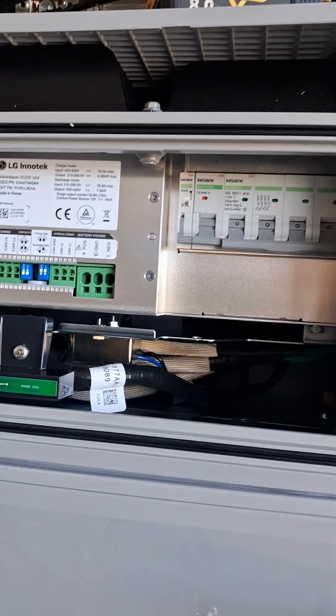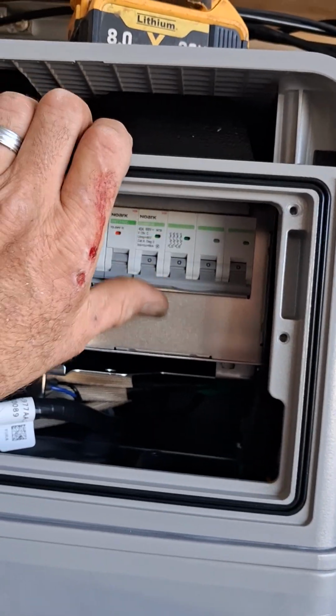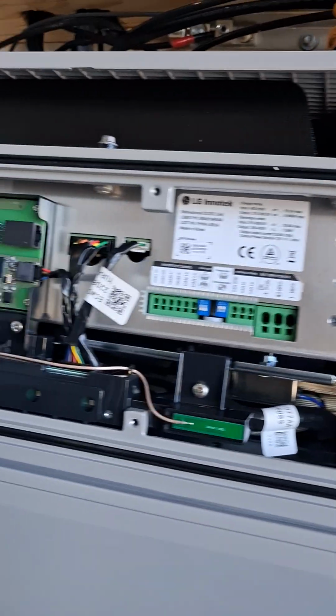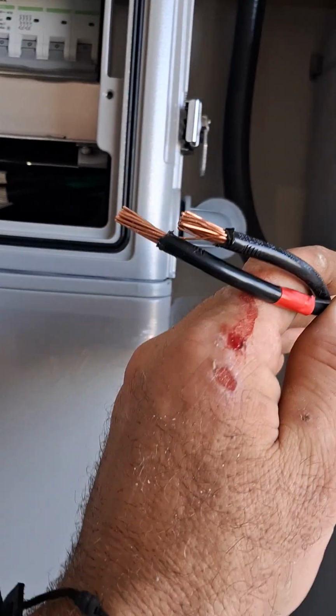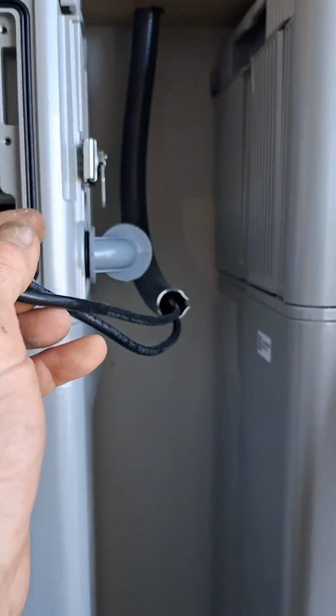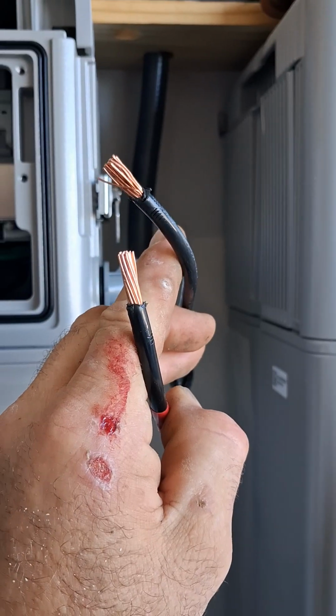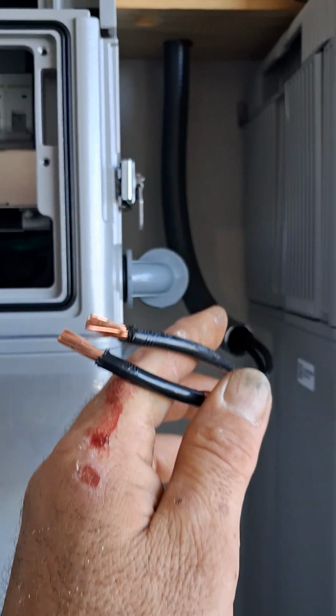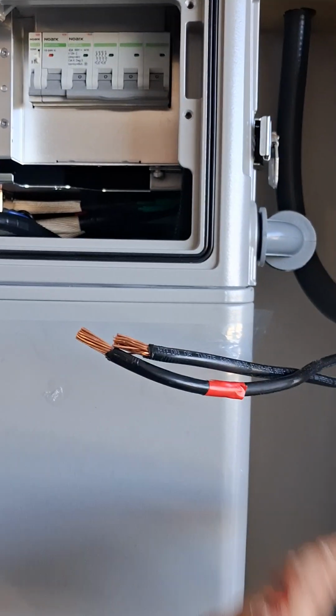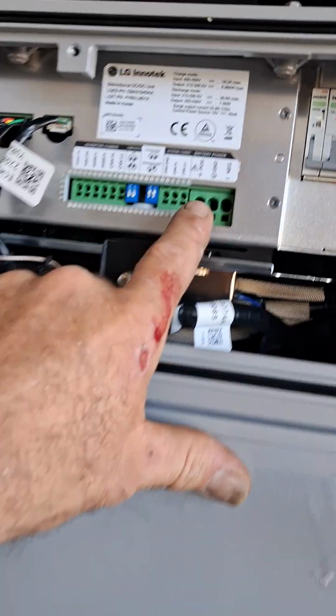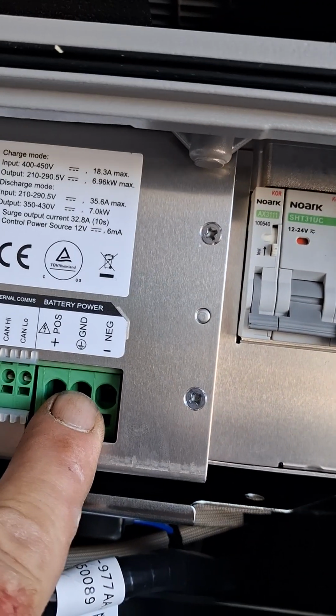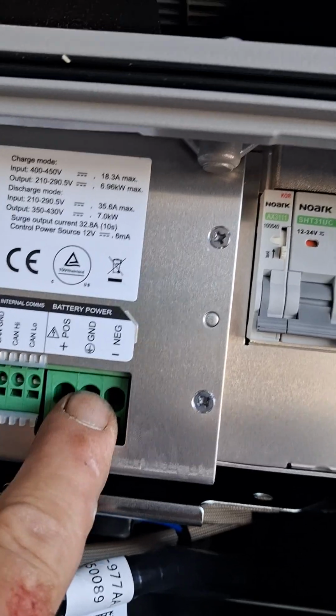This is going to be our main breaker, off and on, operating the 400 volt system. This is the 6 gauge wire that will be coming in, and I need to run a, well, I do have the ground.